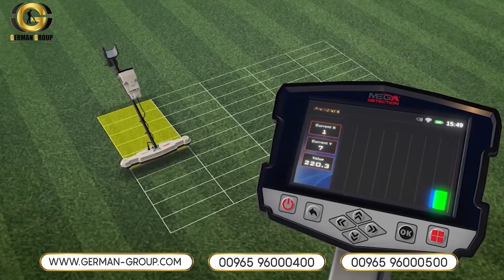After each line of the scanning process is completed, you'll see an alert on the screen, which means you have to start a new scan line. Change your position to the beginning of the next line and then press the Start button located under the handle of the device. On the screen appears a window that includes a grid of cells according to the number of lines and steps previously set. In the right pane, you can see information about the current step, current scan line, and numeric value of the probe during the scanning process.